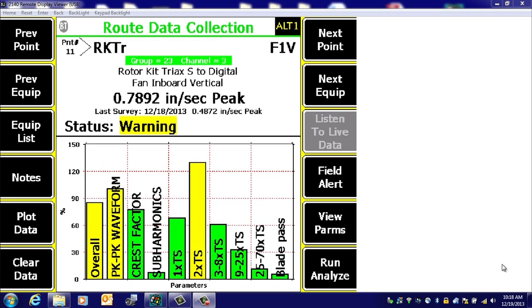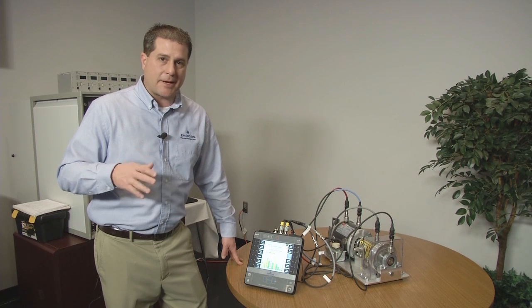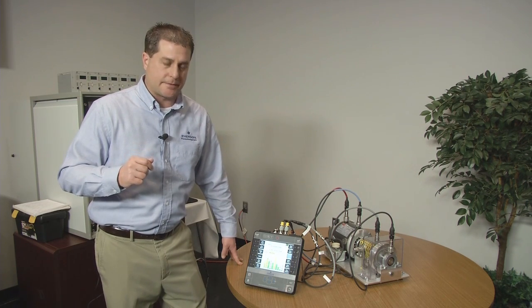And so let's say I just collected this data off this machine and you can see a high two times running speed turning speed peak here. And that tells us, well, maybe I'm suspecting a misalignment condition on this machine.